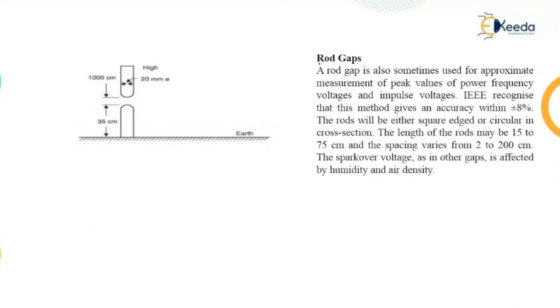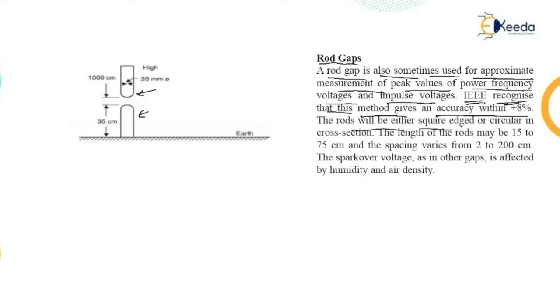The second part is the rod gap. Similar to a sphere gap, a rod gap uses two rods — one grounded and another held by an assembly — with a gap between them. A rod gap is sometimes used for approximate measurement of peak values of power frequency voltage (50 Hz) and impulse voltage. The accuracy of this method is within plus or minus eight percent.